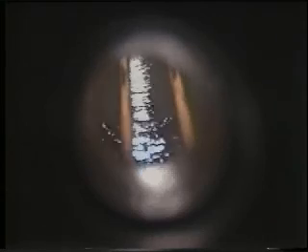You are now looking at liquid carbon dioxide with overlying vapor inside a pressure vessel as it exists at normal storage conditions of approximately 300 psig and a temperature of approximately plus 2 degrees Fahrenheit. The boiling effect observed in the liquid is occurring due to normal heat entry through the insulation of the vessel. The ambient temperature at the time of this test was 70 degrees Fahrenheit. As ambient temperature rises, the boiling effect increases due to the greater temperature differential between the outside and the product. The boiling is always present as long as the ambient temperature is above the liquid CO2 temperature.